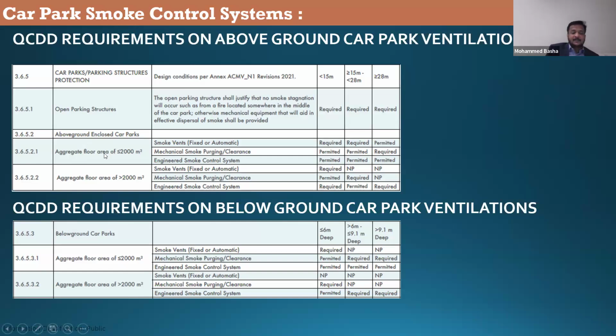Above ground enclosed car parks depend on the area. If the area is less than 2000, some requirements. If the area is more than 2000, some requirements. You can have 3 types: smoke vent system, which is the openings, flaps; mechanical smoke purging or clearance. Purging clearance means it's a post-fire event. Okay, it is not the jet fan systems. You are clearing the smoke after the fire event. That is called smoke purging also. Engineered smoke control system, which is the thrust fan or conventional smoke control system using duct fans. QCDD requirements of below ground car park: aggregate floor area less than 2000, smoke vents are allowed. It is not that you always need to have jet fan systems or bigger fans.